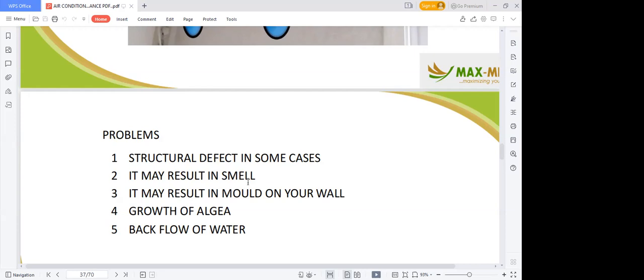If you are using a VRF system and many units are connected together, please tell your installer or your plumber to ensure that after about 2 to 3 meters away from the unit, you install what they call air vents. If air is trapped inside your unit, it can lead to backflow of water. I've experienced it in a building where water was dropping as if it was raining inside the building. We discovered all the units were connected together. There were no air vents. Please take note of that.